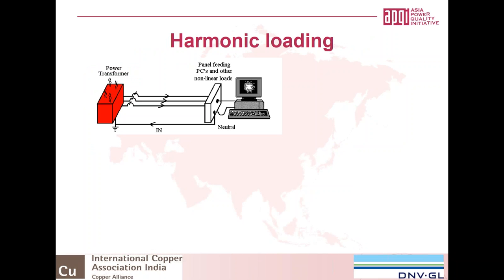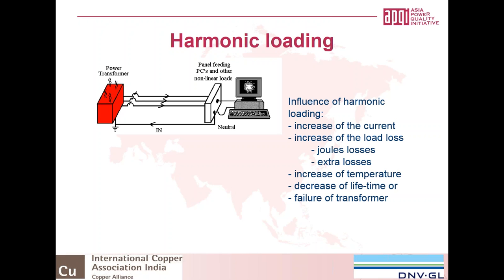Why does harmonic loading have a bad impact? Well, in this case, it's a nice figure I show. You have a power transformer and you have some non-linear loads like PCs, whatever. There will be a loading, of course, of the transformer, and due to the non-linear loads, you will have a higher current in the transformer due to all the harmonics you have. The influence of harmonics on the loading is that it will increase your current. It will also increase your load losses. If your current increases, then of course your DC loss or Joule losses will also increase because your current is higher. But also, as I already mentioned, your extra losses will be very high because they depend on the frequency. And if you have harmonics, you have lots of frequencies which you have to take into account.